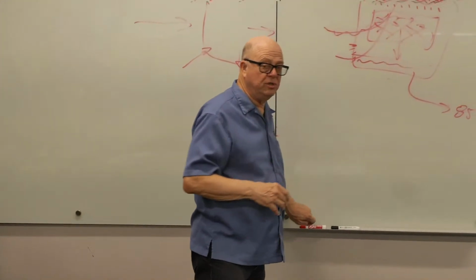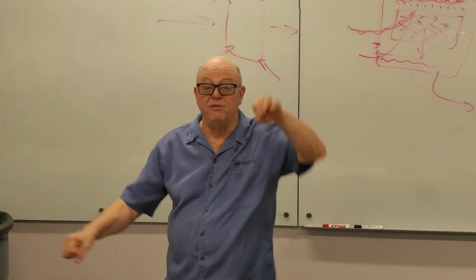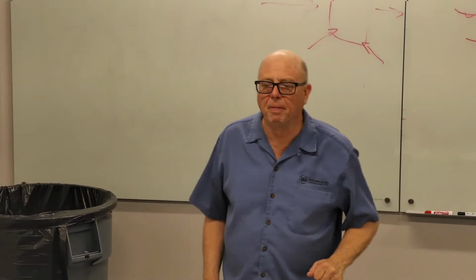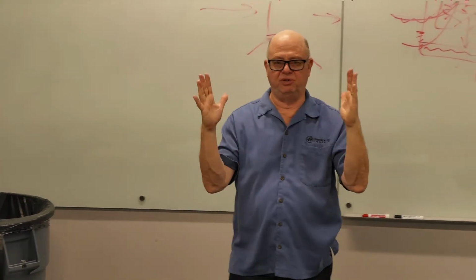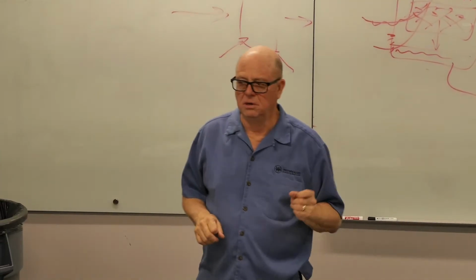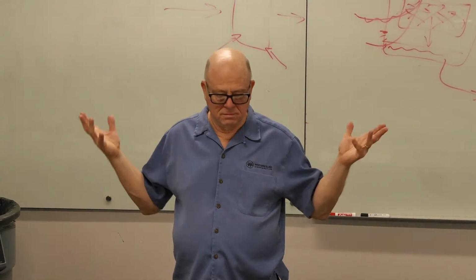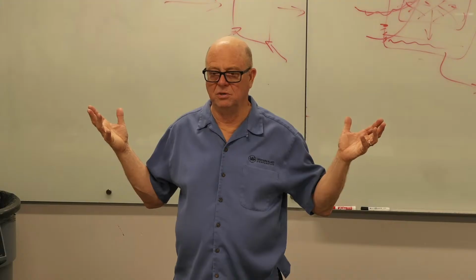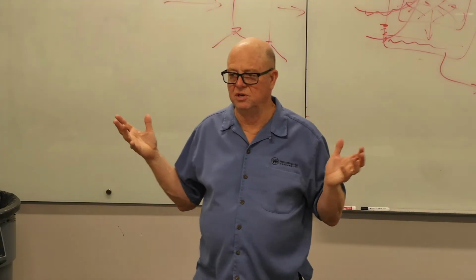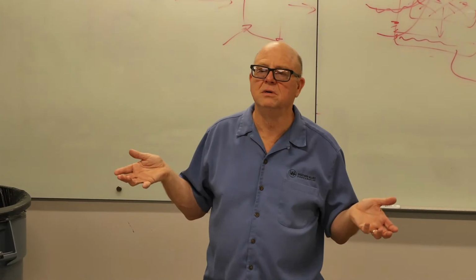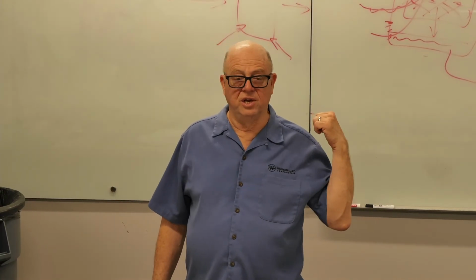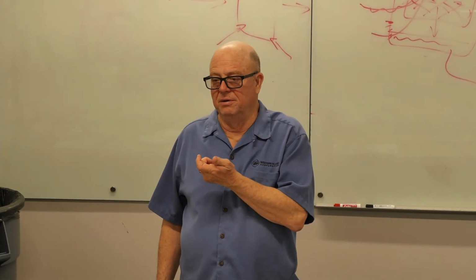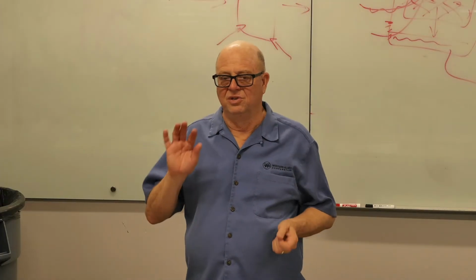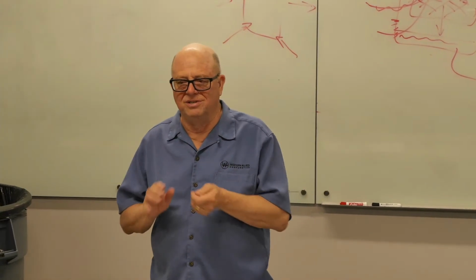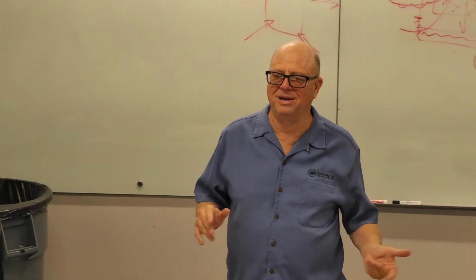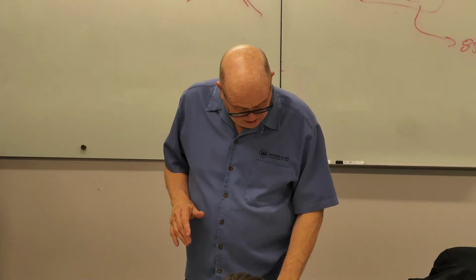Chiller heat exchangers, any heat exchanger you want to think of. Plate and frame heat exchangers, same way. If you're using any kind of a plate heat exchanger, they have to be counterflow. When you don't have performance and nothing else makes sense, the very first thing to look at is, did we pipe it counterflow? And heating is the same way. It's just that heating is typically a 1 or 2-row coil, so you don't lose quite as much. 2 rows, you're probably not going to lose a whole lot. Okay.